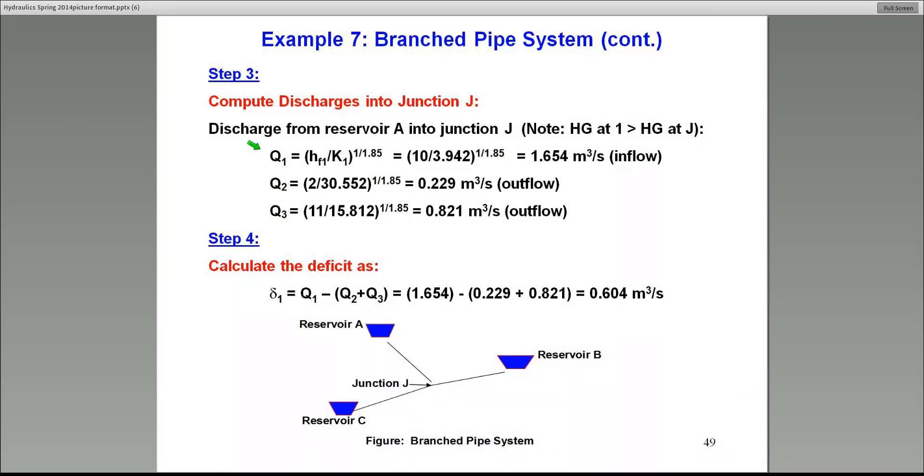For example, the flow in pipe 1 is the head loss of 10 meters divided by the K value for that pipe, and then invert it. This is using the K Q to the power of 1.85 equation. I solve for Q. In this case, it is 1.654 cubic meters per second. Do the same thing for pipe number 2 and 3. Now keep in mind, as I go along, I label them.